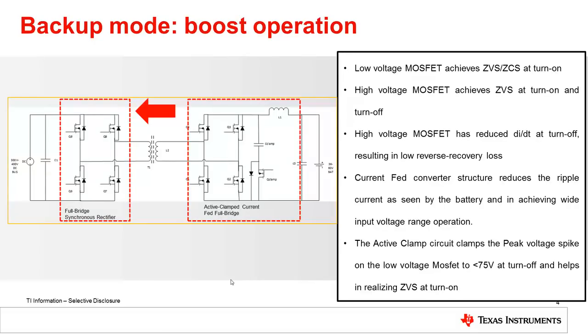In the backup mode, that is when drawing power from the battery and feeding into the 400 volt DC bus, the power stage works as an active clamp current fed full bridge converter. In this mode, the low voltage MOSFET achieves zero voltage switching or zero current switching at turn on, and the high voltage MOSFET always achieves zero voltage switching at turn on and turn off.